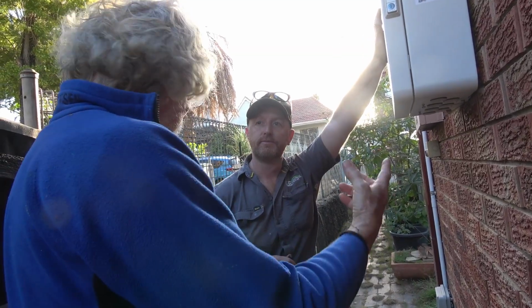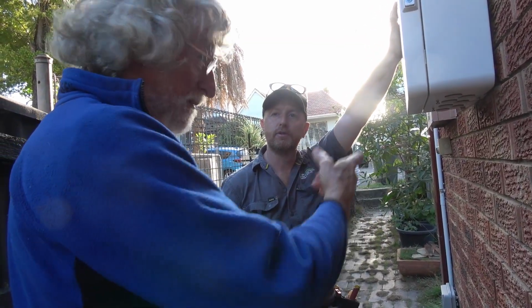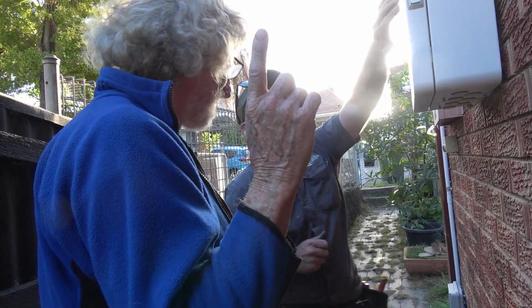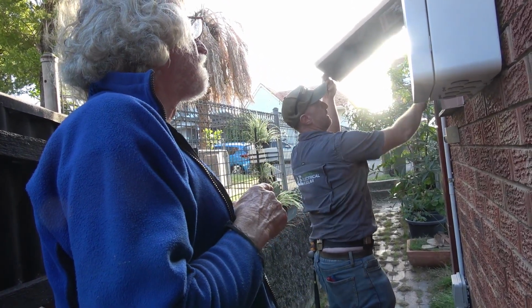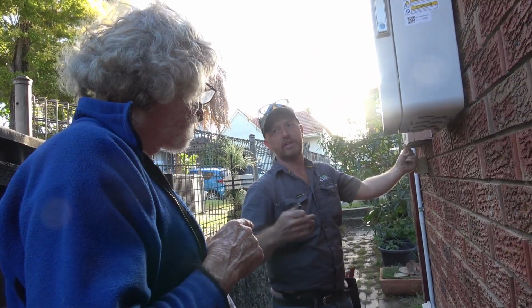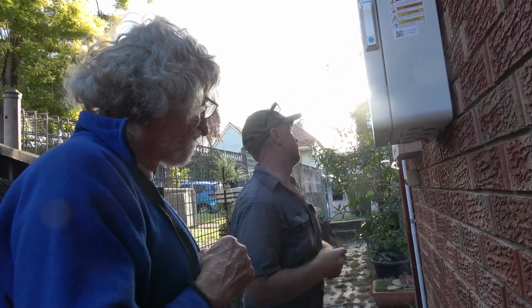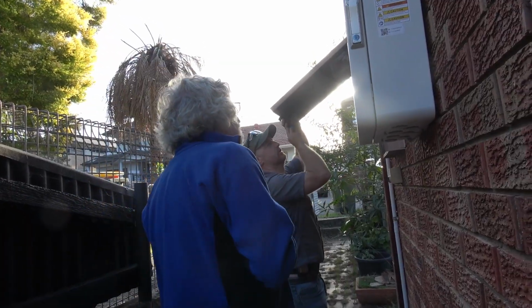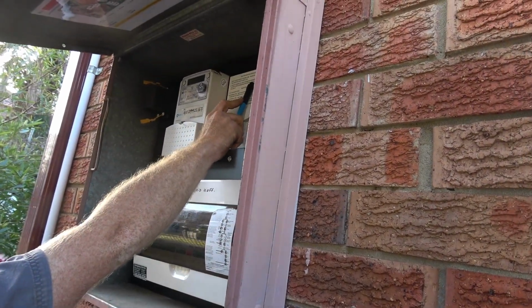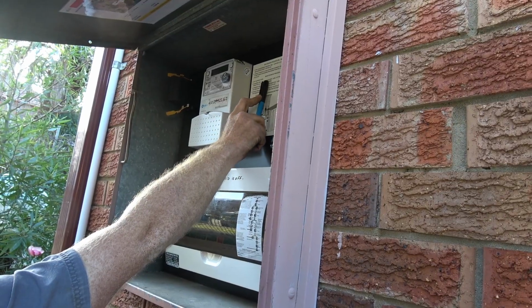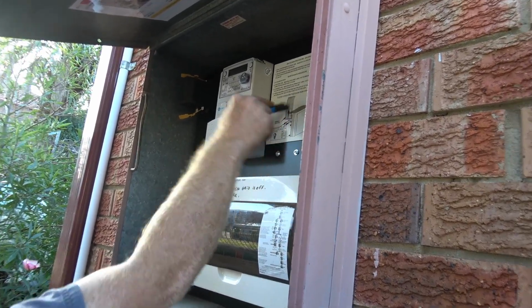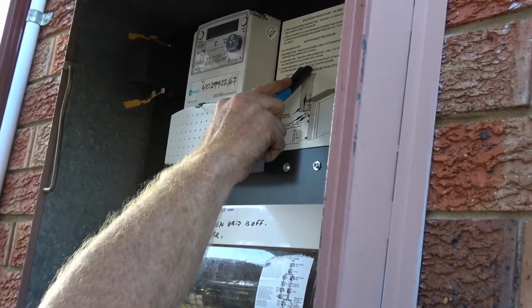But if you get a fire in the house as well, you need to be able to de-energize. Yeah, well, just de-energize it from here. Turn everything off. Like turn off that switch, turn off this switch, turn off the switches in here, turn everything off in that emergency situation. Yeah. The shutdown procedure will tell you how to shut it down. So open your SIG Energy, find that breaker there, and turn it off, and turn off your DC isolator. That's the one that I showed you down there, and then all the other breakers, if you want to get into the board and work on it, it's all documented there.